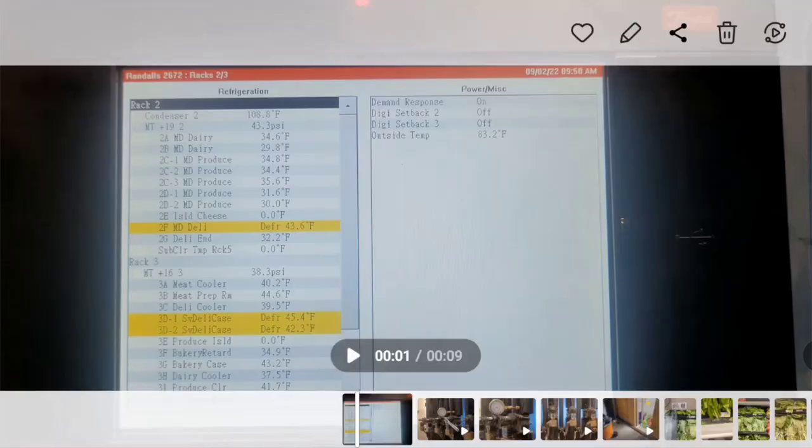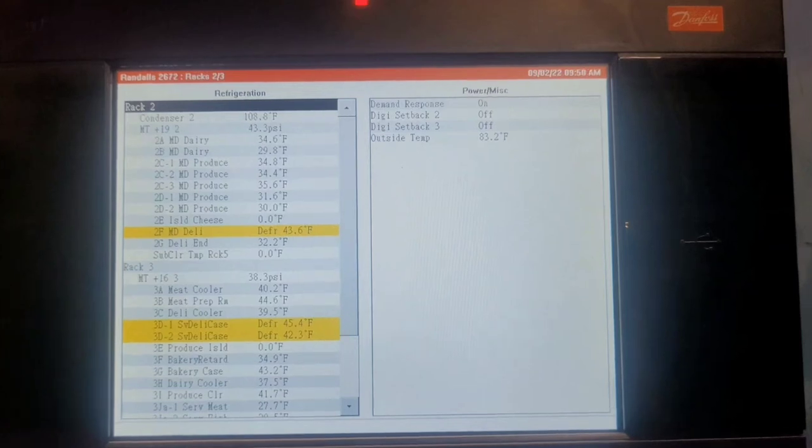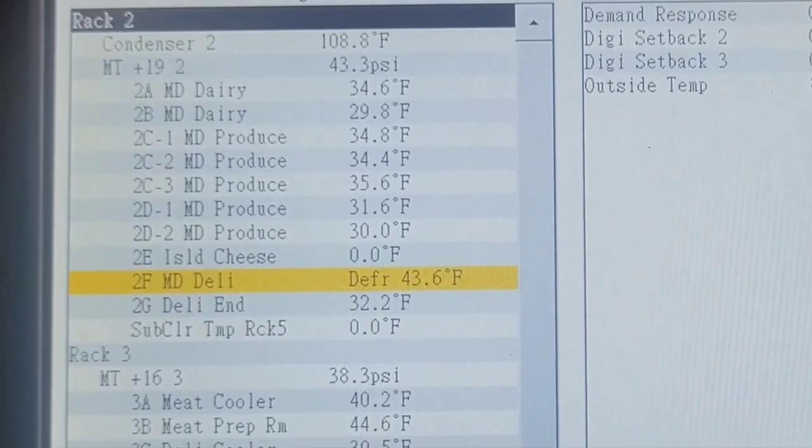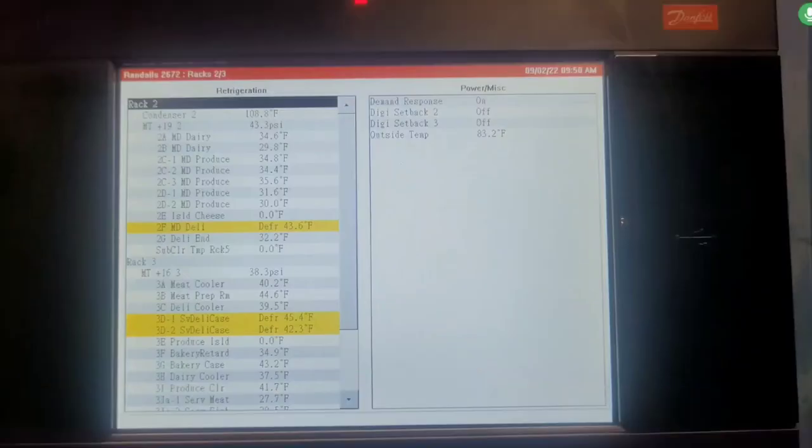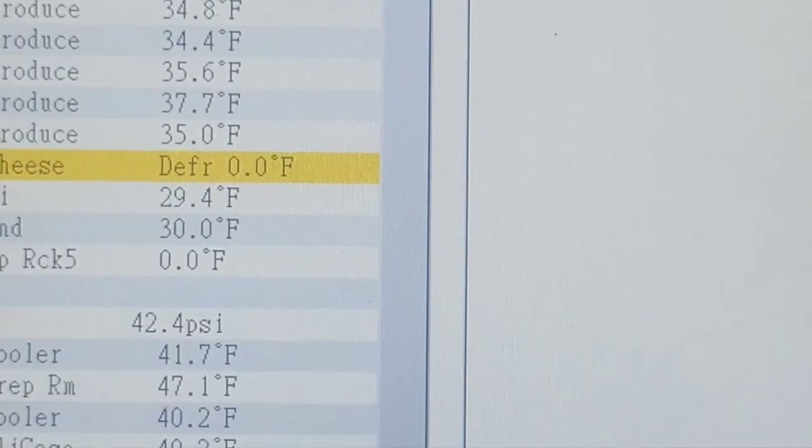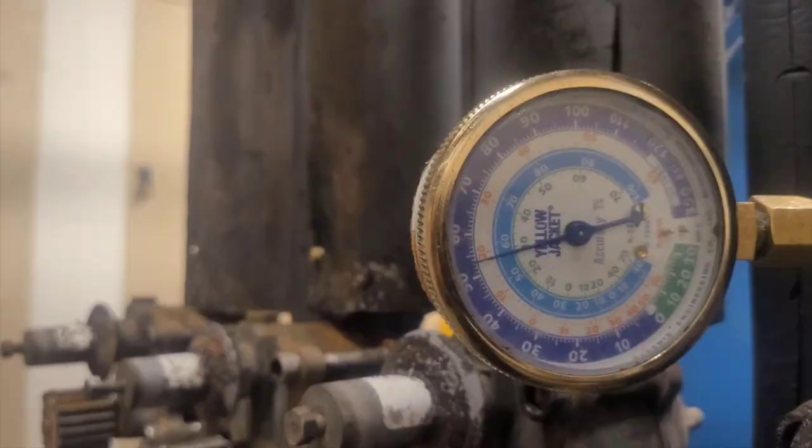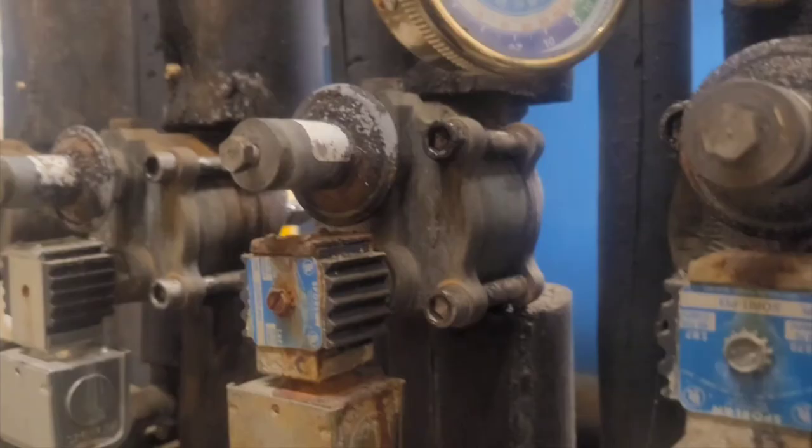At the front of the rack, it's 9:50 a.m., and we're sitting at 2D1, 2D2, at 31 and 30. So at 9:50, it was 31.6 and 30. An hour later, almost 10:47 a.m., it has risen to 37.7 and 35. That's exactly what I was looking for. My suction pressure looks to have stabilized around 54, 55 psi. Here's a little bit better look at the EPR valve.